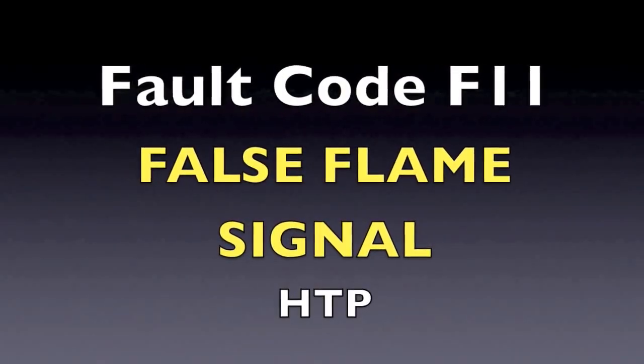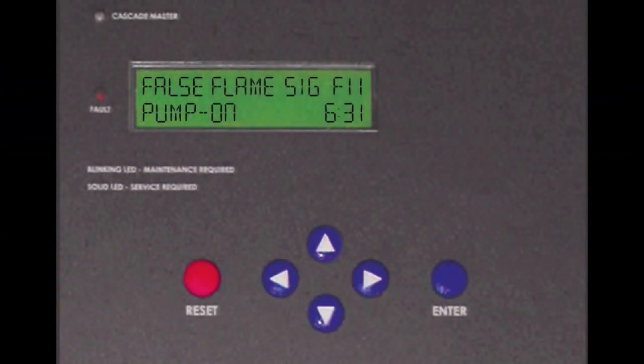If you are getting an F11 code, this indicates that there is a flame signal when the controller is in standby and the heater is not currently operating.